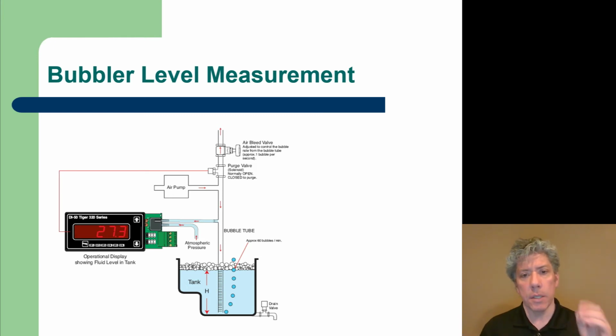What happens is, as the level in the tank drops, the pressure at the bottom of the tube goes down. And so the flow coming out of the air pump now prefers, instead of just all leaking through the bleed valve and just a small amount of it going through the liquid, rather more of that air will go through the liquid, because if you think about it, the air splits off out of that air pump T. Some of it goes up, some of it goes down. It's going to take whatever the path of least resistance is. And so as the resistance decreases to go through the bubble tube and down through the liquid and back out, more is going to go that way. And effectively what ends up happening is the pressure between the air pump and the bottom of the tank tube decreases, and that pressure can be sensed. So you see a little indicating transmitter there on the left that's measuring the pressure at that bubble tube, or in the bubble tube, and transmitting it.